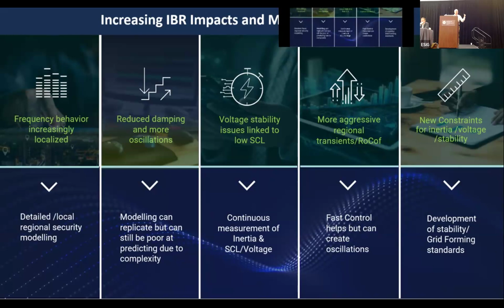If you take an average of the frequency across the system as an output of your model, that'll tell you the frequency is fine. But if you actually look at the frequency at each node on the system, it's going to be completely different everywhere. And that mindset shift, if I could give you one thing today, is that you need to remember the frequency is different everywhere and increasingly localized. And John, I know that adds to your headaches, but you're just going to have to live with it.